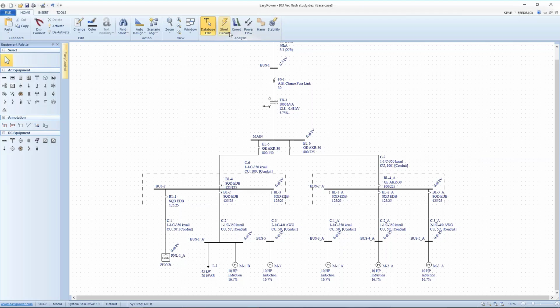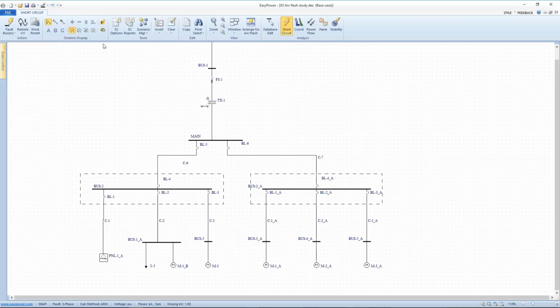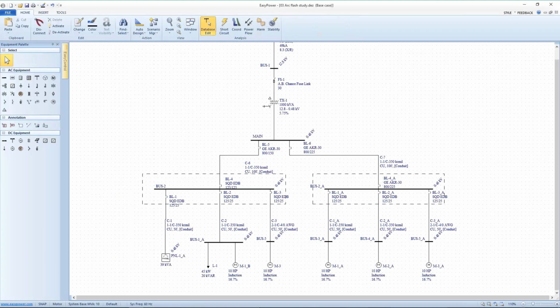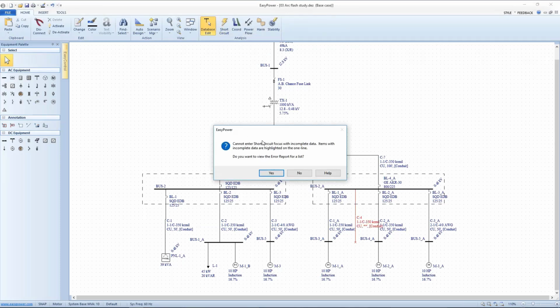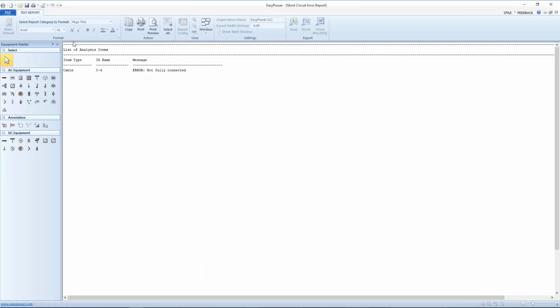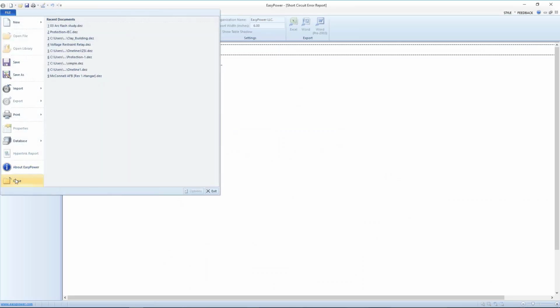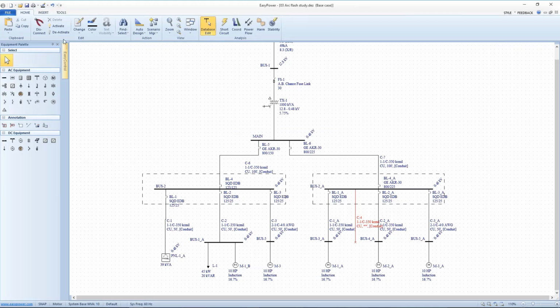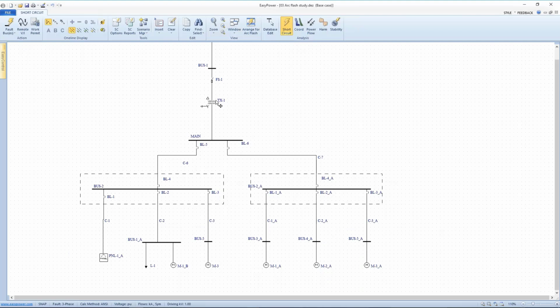Once we've got our data entered, we're able to go to short circuit focus. Now, for those of you that haven't used the tools, one of the nice things about EasyPower is that if I have a lack of data, let's say I had a cable out here that wasn't terminated or populated with data, and I try to go to short circuit focus, it's going to say, Jim, are you sure you know what you're doing? Do you want to see an error list? And certainly I do, and it points out what's going on. So I'm able to go back to my one-line diagram and undo the last step that I did. So I'm going to take that cable out. Now that I've collected the data, I've populated all the different points, drawn my one-line diagram, and I have no errors, I'm ready to go to short circuit focus.